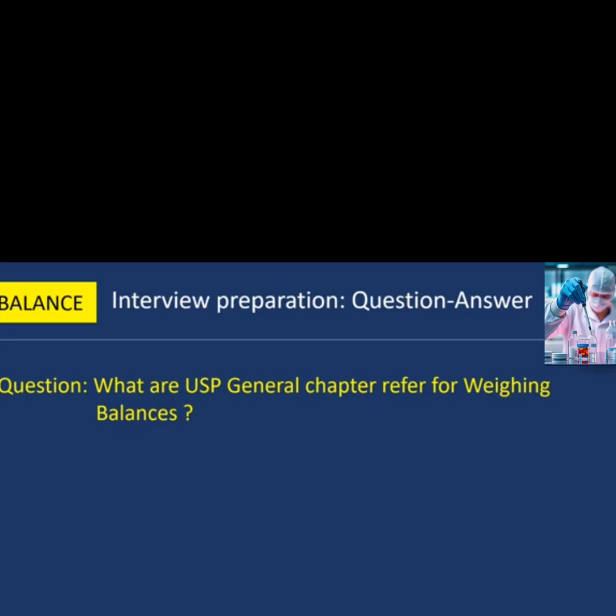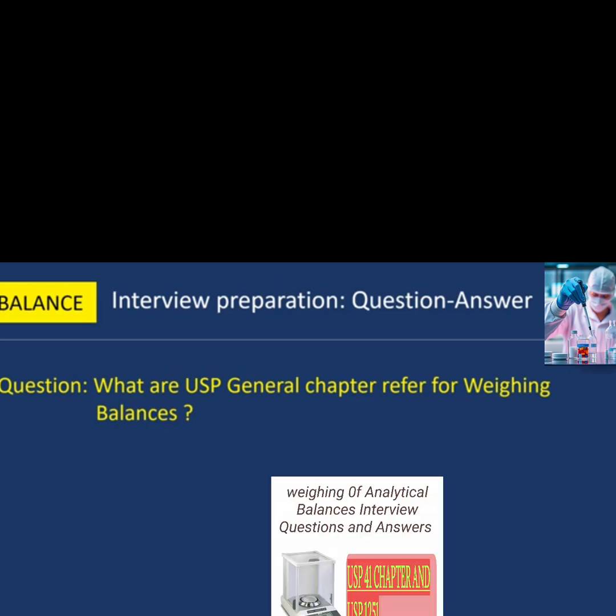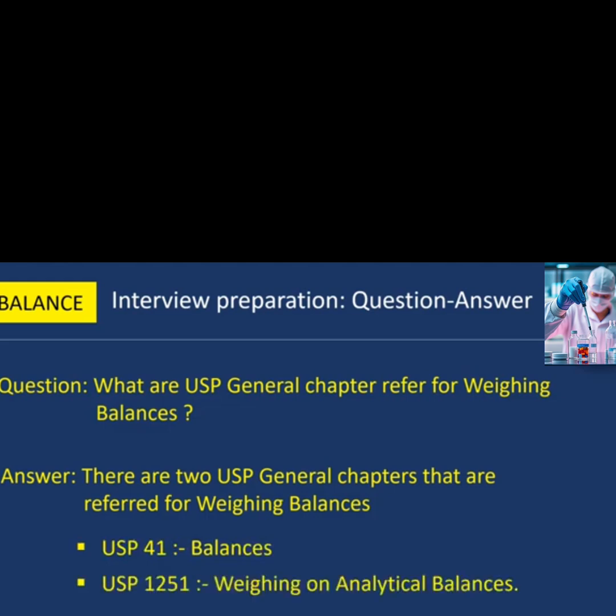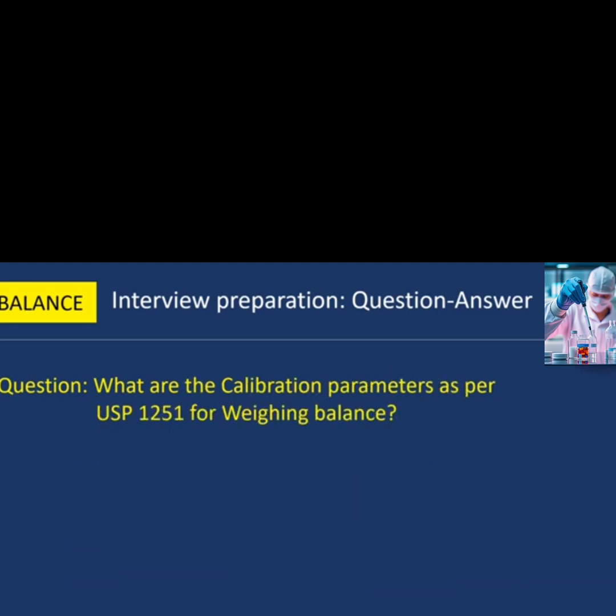First question: what are USP general chapters referred for weighing balances? There are two USP general chapters referred for weighing balances. First is USP 41 Balances, and second is USP 1251 Weighing on Analytical Balances.